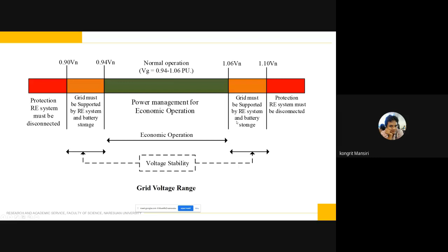Yes, what is the result? In the case of the distribution, in the nighttime with no PV production, the grid voltage is okay, in the acceptable range, 0.96, within the PEA requirements. But on the other hand, when we have high PV penetration, if the 8 megawatt PV power plant production is over 6 megawatts, the grid voltage is over the upper limit of PEA. So how do we balance this? We have distribution, battery storage, and demand side management. What is going to happen? Let's see.